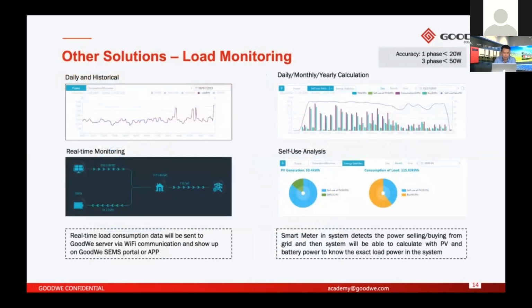And this one is a solution for load monitoring, also called consumption monitoring. This function is actually a default function of hybrid inverters and AC coupled systems, because it's realized by the smart meter, and a smart meter is a default component for hybrid inverters, AC coupled inverters, or any storage inverters. So this function will be realized automatically if you connect the whole system correctly.